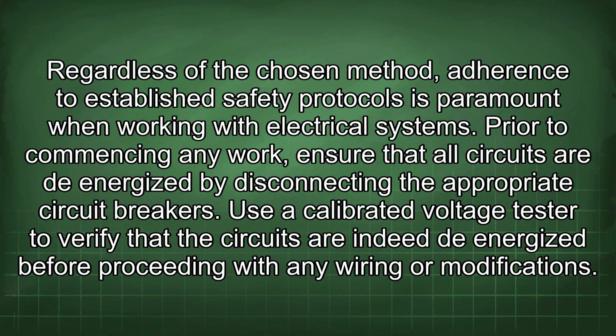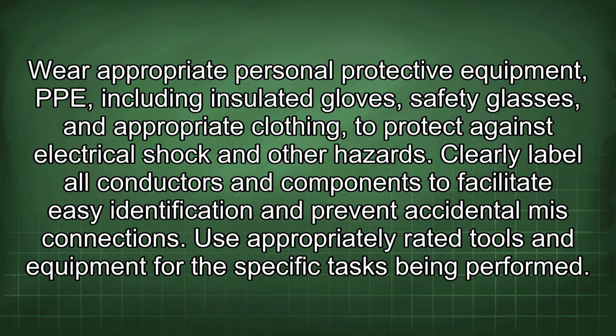Regardless of the chosen method, adherence to established safety protocols is paramount when working with electrical systems. Prior to commencing any work, ensure that all circuits are de-energized by disconnecting the appropriate circuit breakers. Use a calibrated voltage tester to verify the circuits before proceeding with any wiring or modifications. Wear appropriate personal protective equipment, including insulated gloves, safety glasses, and appropriate clothing to protect against electrical shock and other hazards.